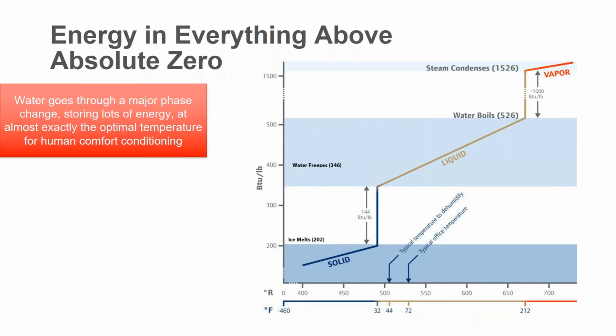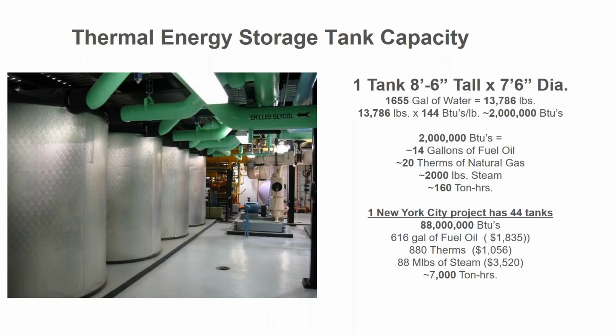And this phase change happens really close to where we need it for comfort cooling. Okay, so it just happens to be that way. It also goes through another phase change, obviously, from water to vapor, and that's an even bigger phase change. That's about 1,000 BTUs per pound. But those are the two major phase changes. So, these as ice storage tanks. Well, let's look at them as thermal storage tanks, right?